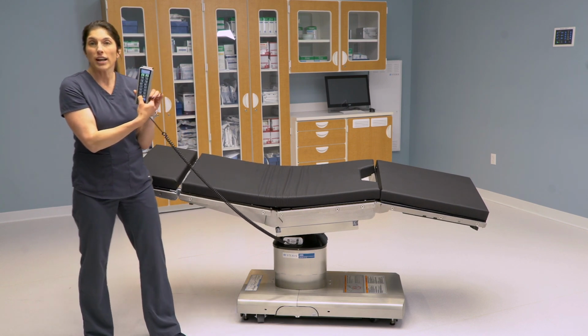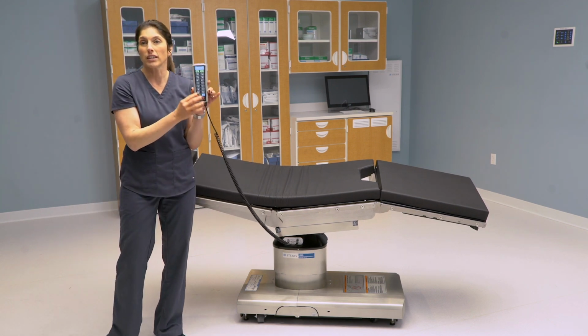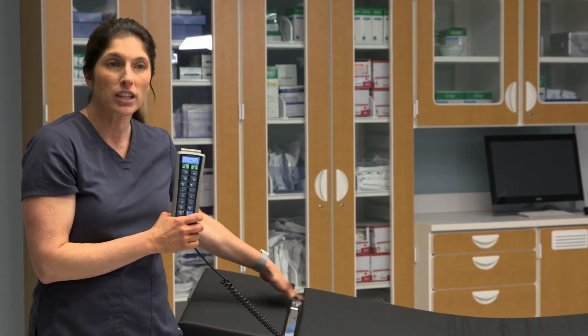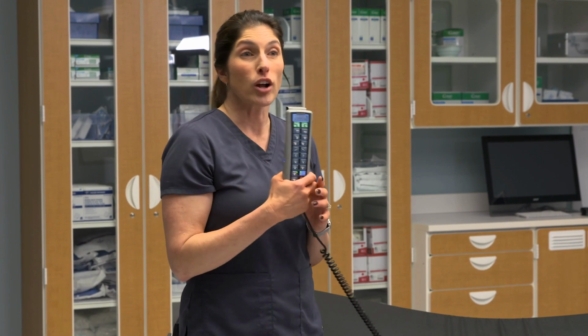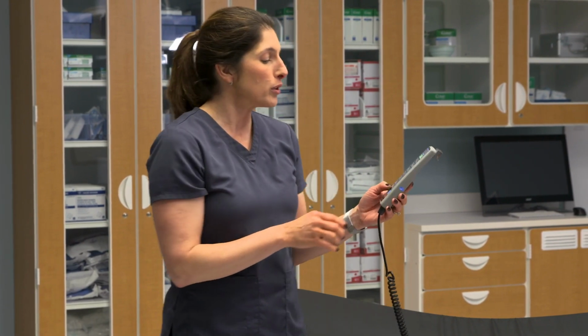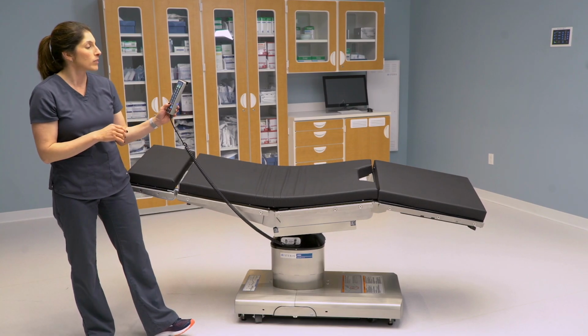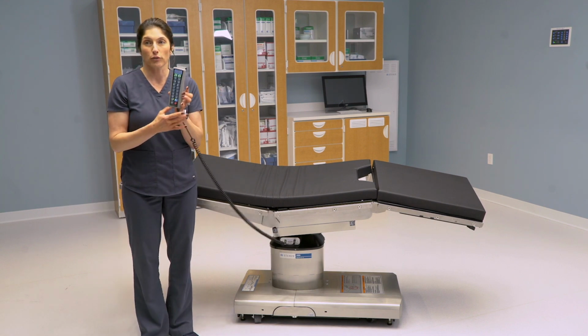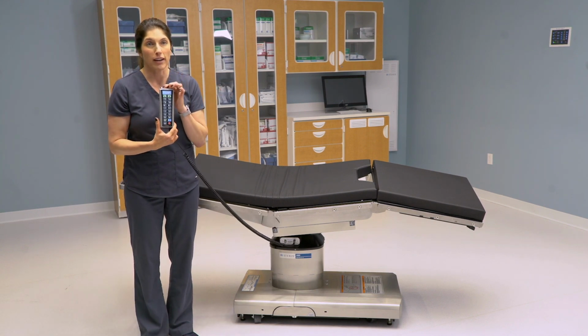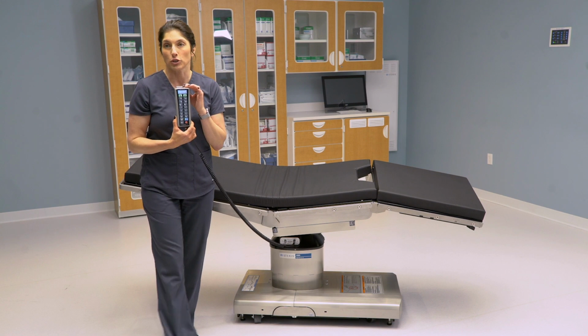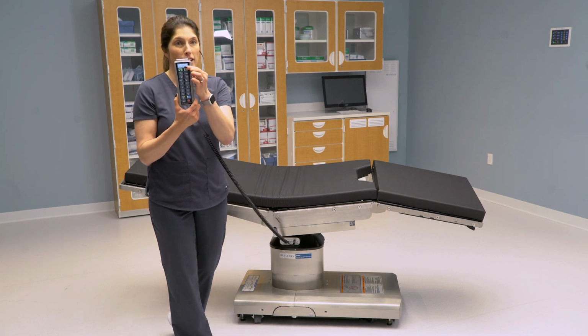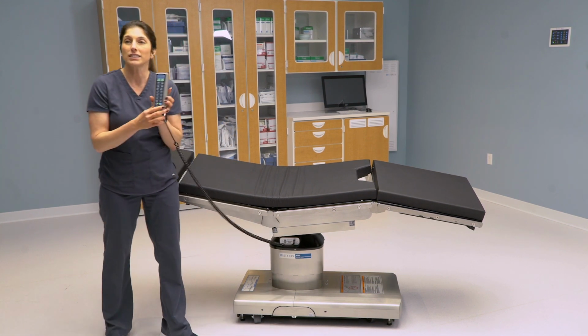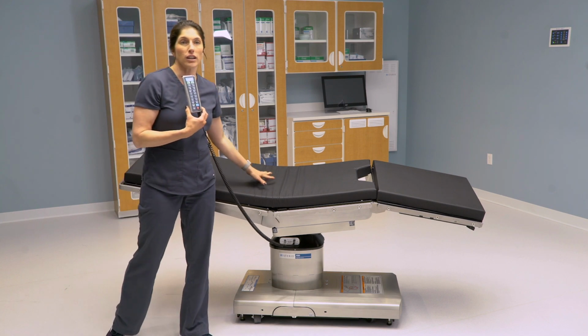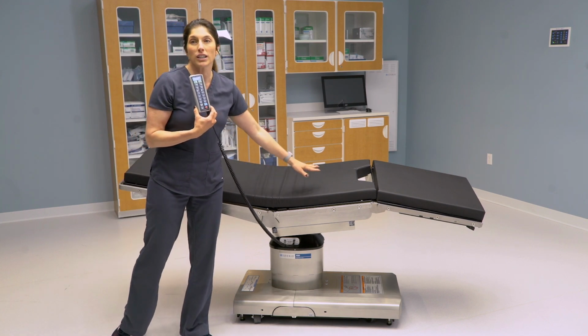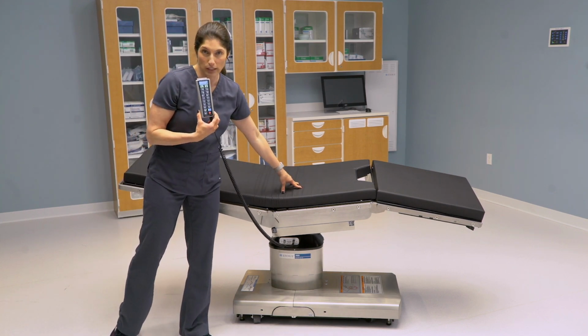And kidney bridge. So that's another thing that's different from your 3085. The kidney bridge on your 3085 is the manual crank located under the head section. And on the 4085, it's automatic on your hand control. So you can press and hold kidney up, which brings us to another feature on the 4085 that is different from the 3085. We call it the auto limit sensor, ALS for short, on the hand control. And what that is, it's telling us if any section of the surgical table is going to collide with another section of the surgical table.